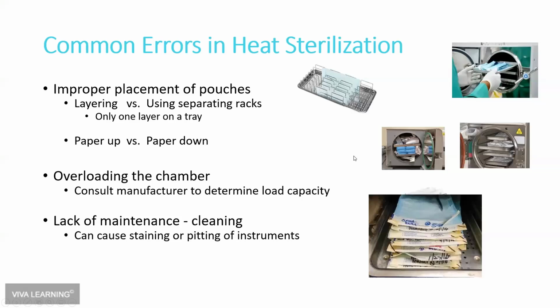The best thing to do, according to the manufacturers of the pouches and the sterilizers, is to either have one single layer of pouches on a tray, or you put them in racks where it keeps them on their side, or you get them manually kind of on their sides without a rack, like the picture on the upper right-hand side. So we don't want to overload. I love this picture in the center. I don't know how anything could possibly get sterilized in that particular sterilizer. So this is one of those things where we either need additional sterilizers, or we need to look at our throughput capacity in the sterilization area.